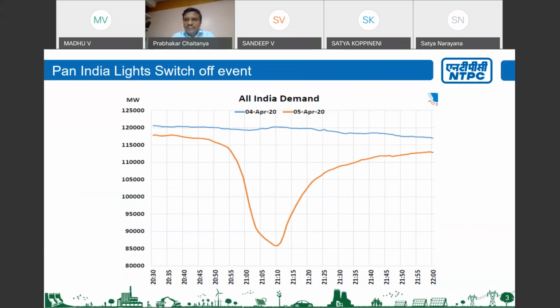When our PM announced to switch off the lights, we anticipated there would be a 10 to 12, or 12 to 14 gigawatt dip in total power generation. But to our surprise, the decline in power generation was around 31 gigawatts. Normally, if a 500 megawatt unit trips, there is a change in frequency of about 0.1 Hz. If around 28 gigawatts of power had failed suddenly, it could have created a much greater havoc.